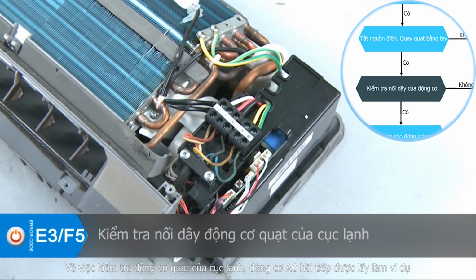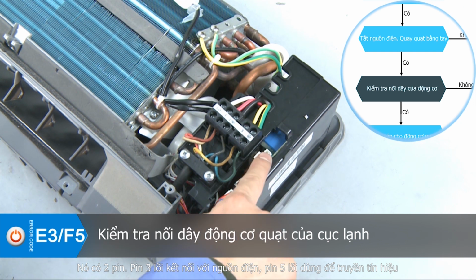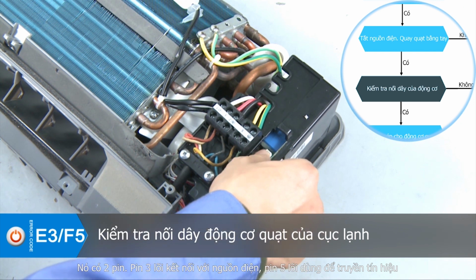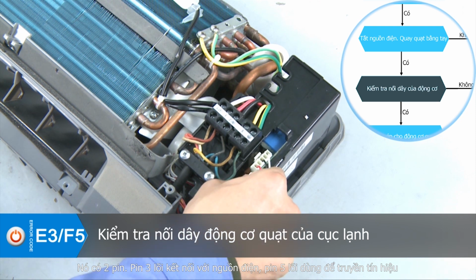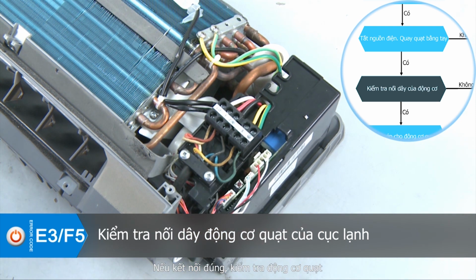Examination for the indoor fan motor. Taking AC motor with feedback as an example, it has 2 pins. Separately, the 3-core pin connects to the power supply, and the 5-core pin is used for signal transmission. If the connection is correct, check the fan motor.